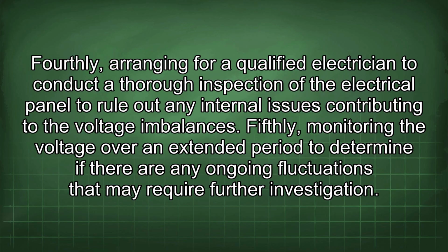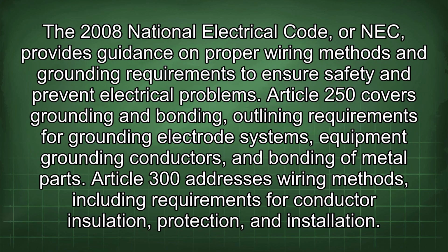Fourthly, arranging for a qualified electrician to conduct a thorough inspection of the electrical panel to rule out any internal issues contributing to the voltage imbalances. Fifthly, monitoring the voltage over an extended period to determine if there are any ongoing fluctuations that may require further investigation.